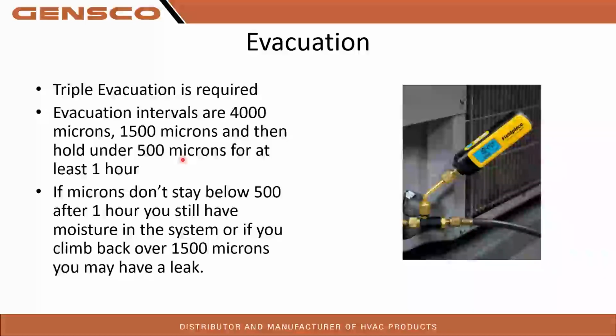I'd recommend trying to get down below 500 as much as you can. I know on new job sites, getting down to 200 or 300 microns is pretty easy. If you're doing repairs on existing equipment, it might take a little bit more work. But you want to get down under 500 microns, shut your hoses off, shut your pump off, and do a 1 hour decay test. So the goal is to hold under 500 microns for at least 1 hour.